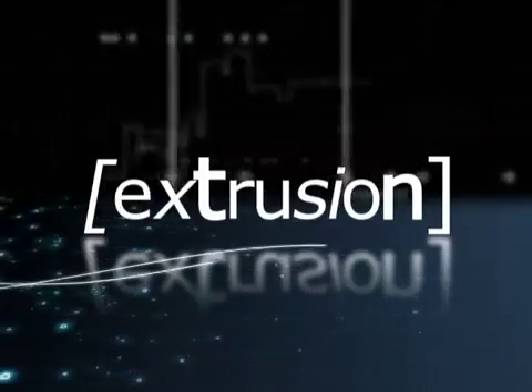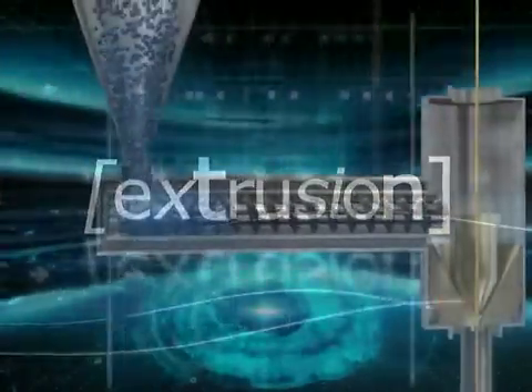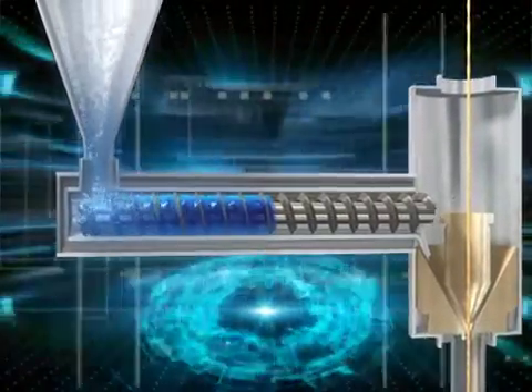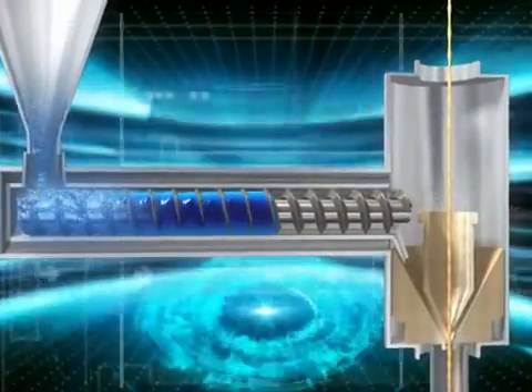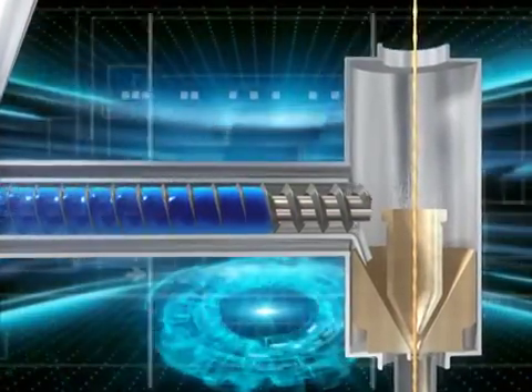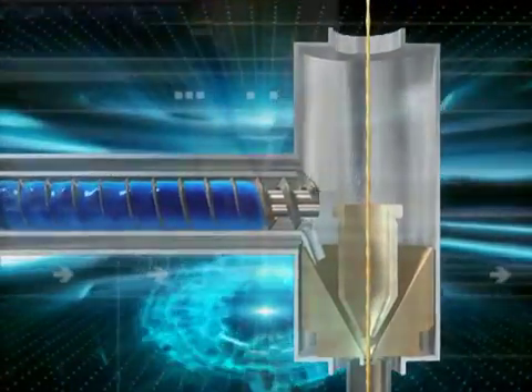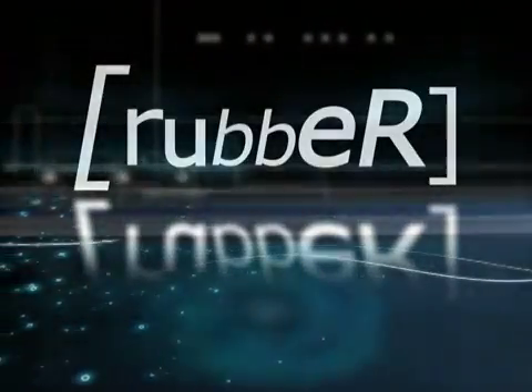After manufacturing the conductor, the copper with a precise cross-section is subjected to an extrusion process. This mainly consists of compressing the material in a doughy condition, forcing it to pass through a mould template which reproduces the external shape of the piece to be obtained. If the cross-section is hollow, a core will be present, reproducing the outline of the internal cavity. On leaving the mould, the material is cooled, or in the case of rubber, subjected to vulcanization.